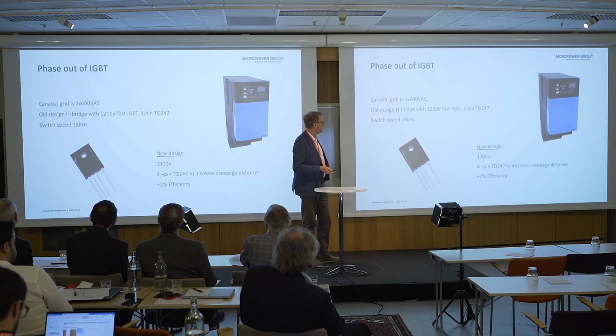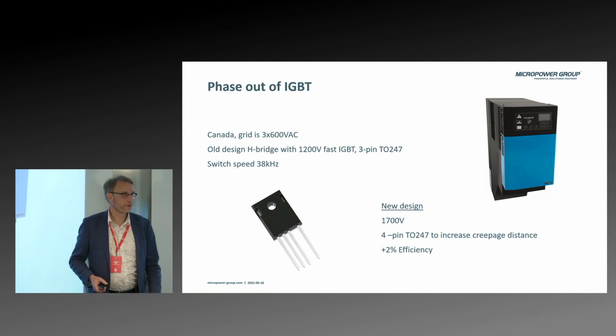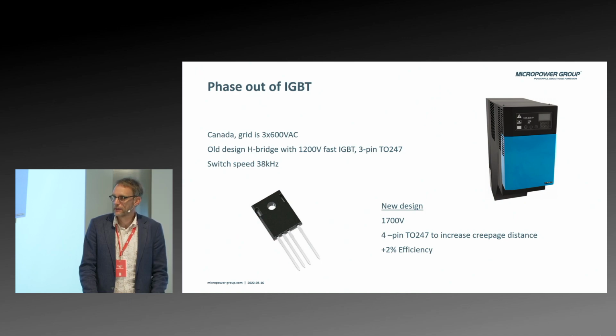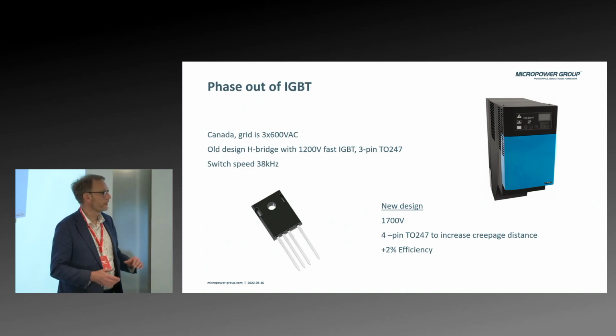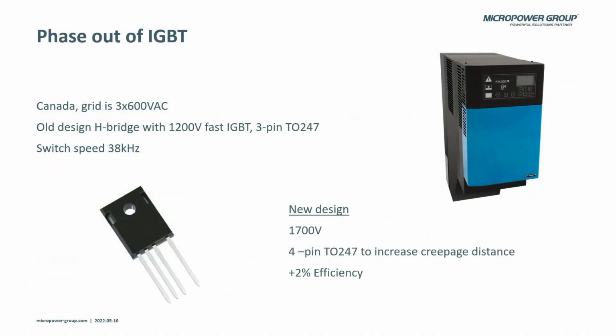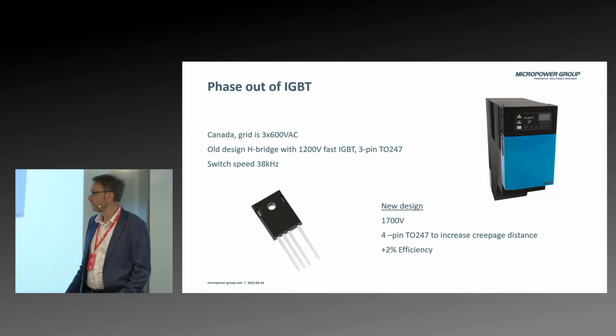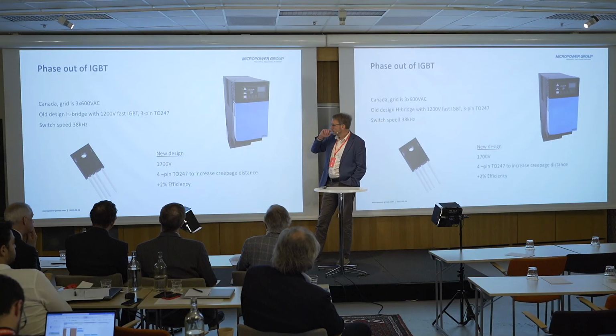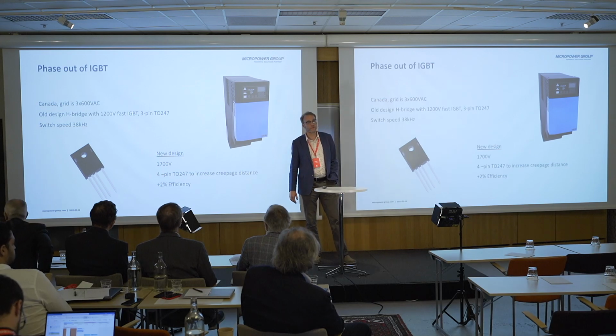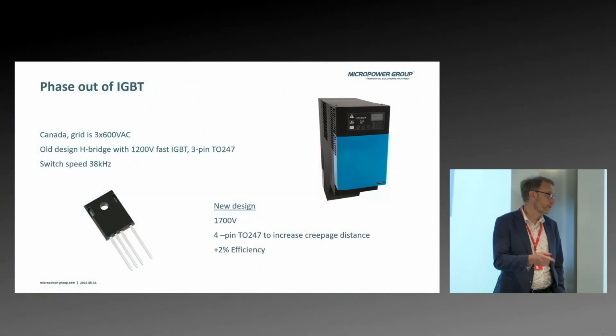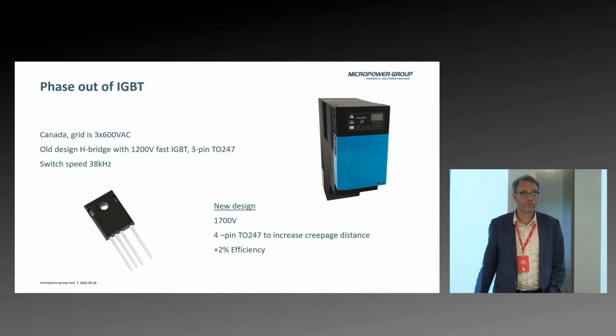Another change we're making right now concerns Canada — the grid there is 600 volts, which is a bit problematic; it's the only country I know of with 600 volts as their standard three-phase voltage. Today we use 1200 volt IGBTs, the same IGBT chip as the discrete version, also with lowered switching speed. We're now looking into going up to 1700 volts to get more margin, since 1200 volt components on a 600 volt grid is a bit on the edge — we see more failures there than in other countries. Also, the old 3-pin TO-247 package is kind of crazy given the creepage distances between pins at that voltage level, so we're moving to a 4-pin component as part of this change.